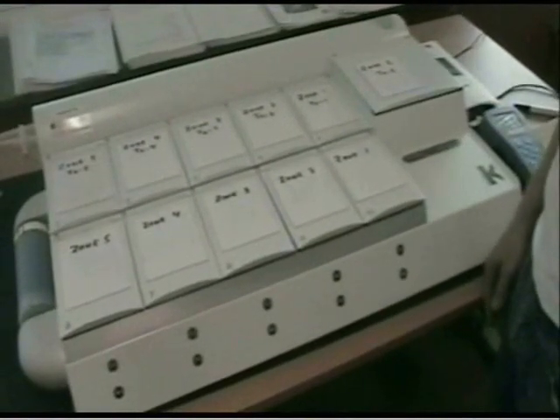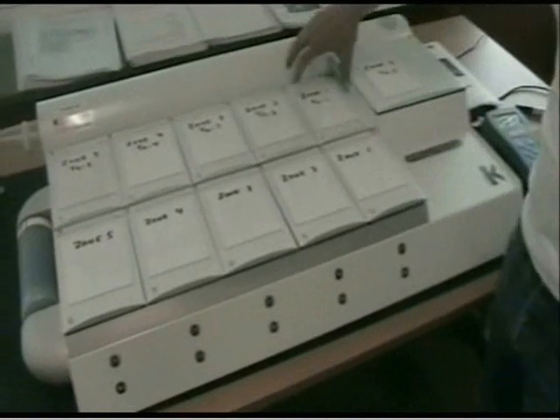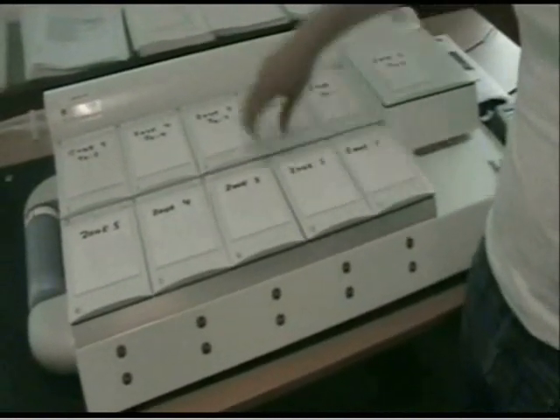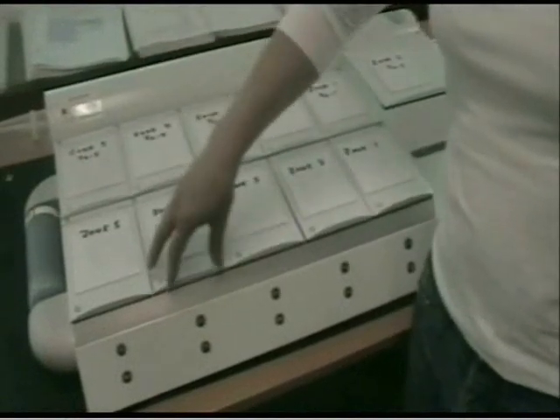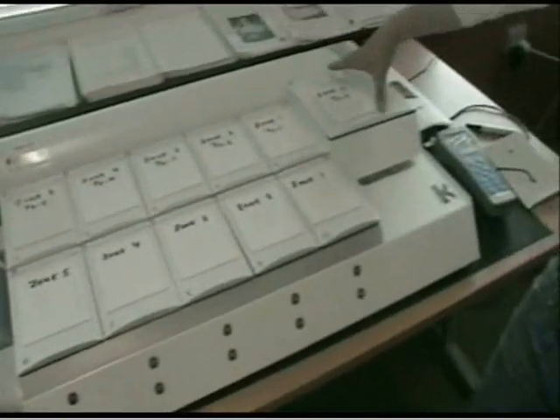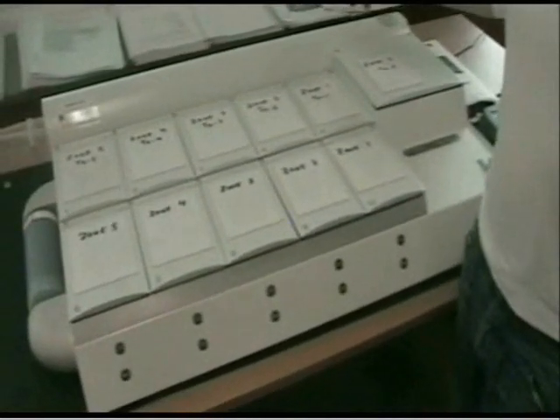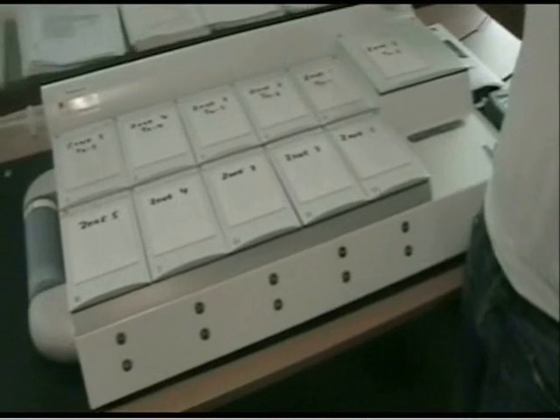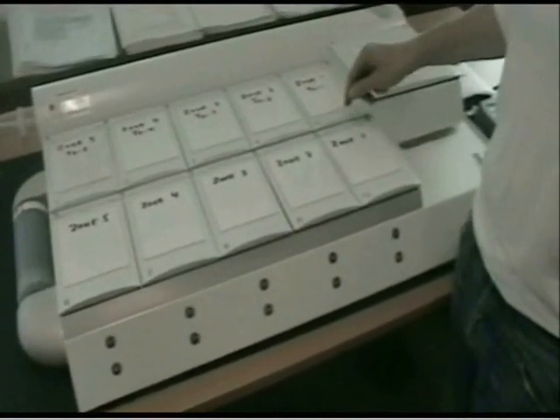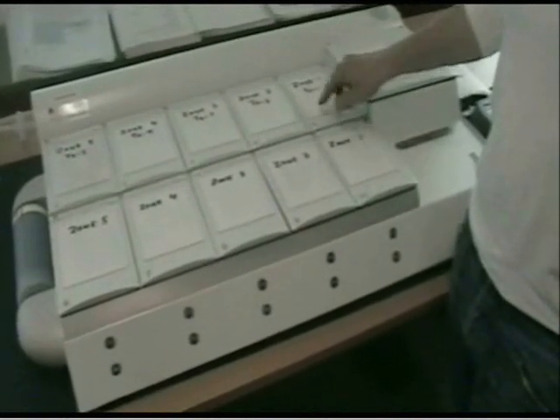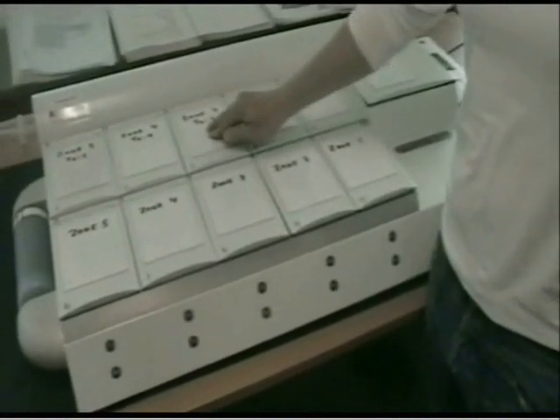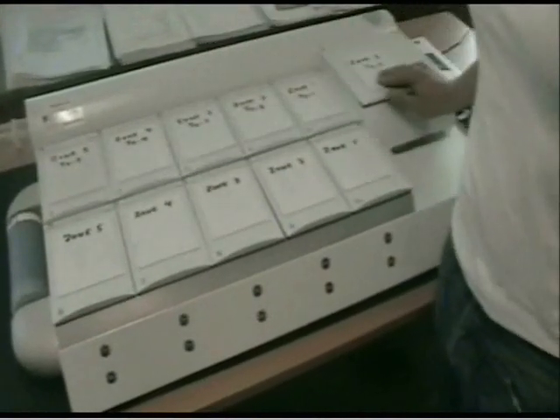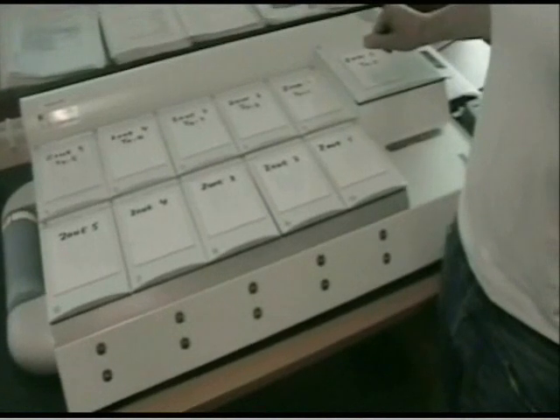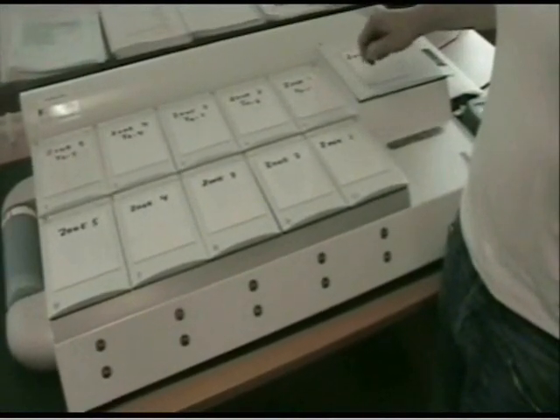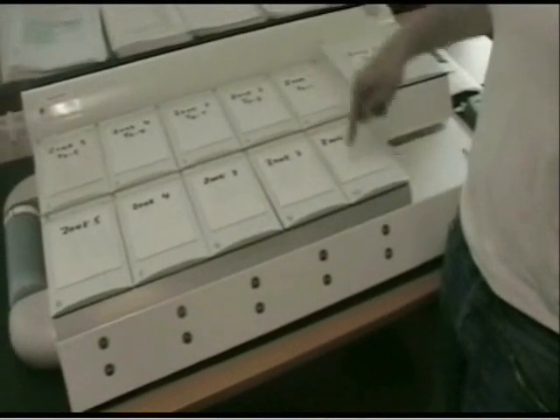There are six separate controls of temperature on the G185 incubator, so that's 6 zones. One zone is here, zone 2 is here, zone 3 is here, zone 4 is here, zone 5 is here, and zone 6 is this compartment over here. Each zone is regulated independently, and it's got its own calibration value, which is called a tune value. So this is tune 1, and this is tune 2, tune 3, tune 4, tune 5, and tune 6. These we will access in the menu later on when we do the adjustment. You cannot change the temperature inside one zone, so it's regulated as one.